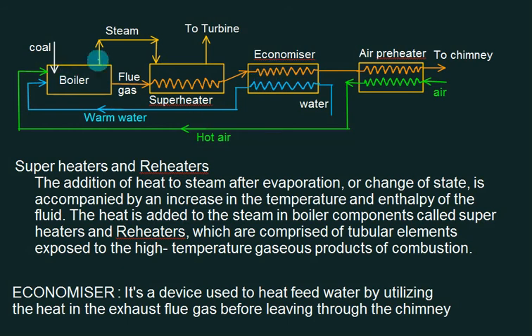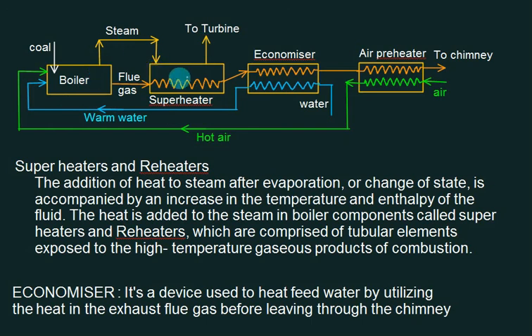In the boiler, we assume that the steam formed is dry and saturated. If we want superheated steam, we use a superheater. So we have boiler, superheater, economizer, and air preheater. In the air preheater, we raise the temperature of air by means of flue gases. In the economizer, we raise the temperature of water fed to the boiler. In the superheater, we convert the dry saturated steam into superheated steam, which is given to the turbine.